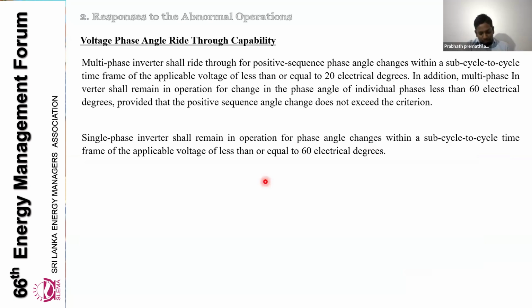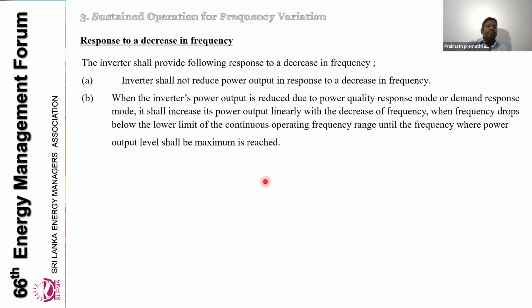And the next one. Another disturbance ride through is the voltage phase angle. In single phase and three phase inverters, up to 20 electrical degrees, it can ride through within a sub-cycle to cycle time frame. If the phase angle change is less than or equal to 20 electrical degrees, it has ride through capability. And even single phase inverters shall remain in operation for phase angle changes within the sub-cycle to cycle time if the applicable change is less than or equal to 60 electrical degrees. This facility is also available in inverters, and we can use it if the voltage phase angle changes due to some disturbance.